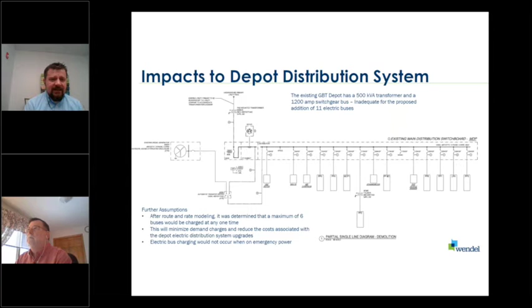So the next slide shows after the modifications, you could see the equipment that's outlined with the red boxes. That's the additional equipment that was needed to accommodate the charging. So we went from 1200 amp switchgear to 2500 amp switchgear with a 1500 kVA transformer from the utility, triple the original size. And again, the red boxes indicate the new equipment. So we knew 11 buses was the goal. And after discussing the project with the local utility there, they advised us that the maximum service that the utility would be able to accommodate could only handle 6 chargers, 6 buses at the same time.